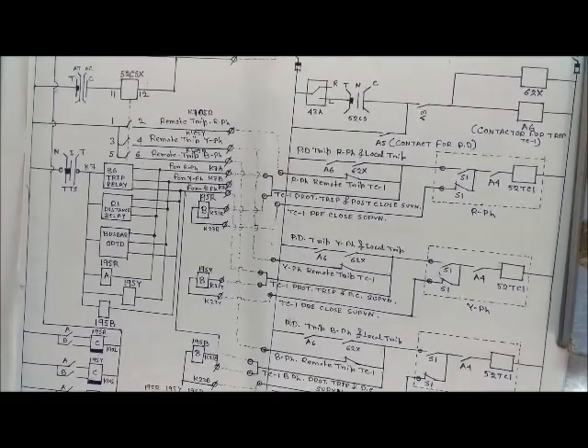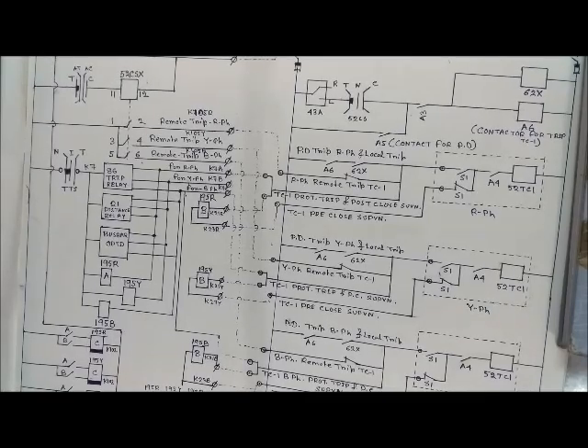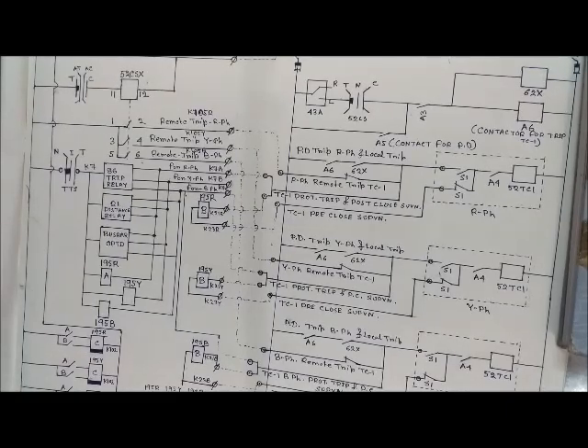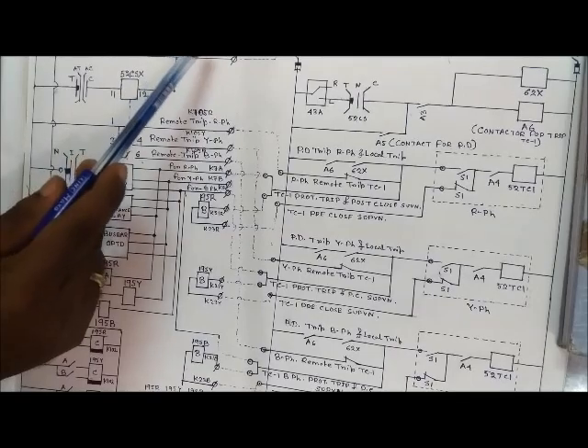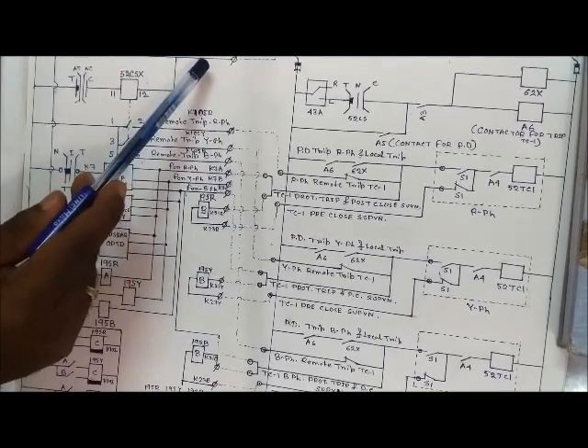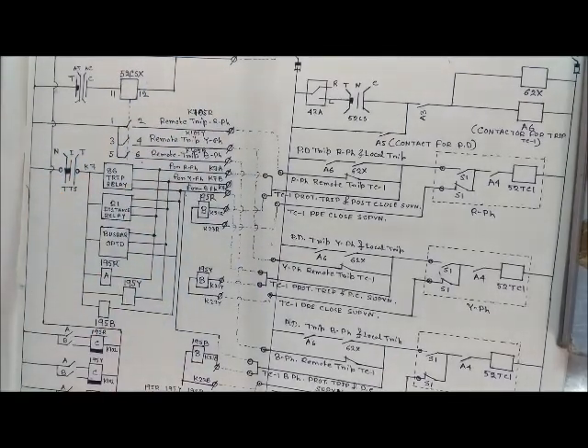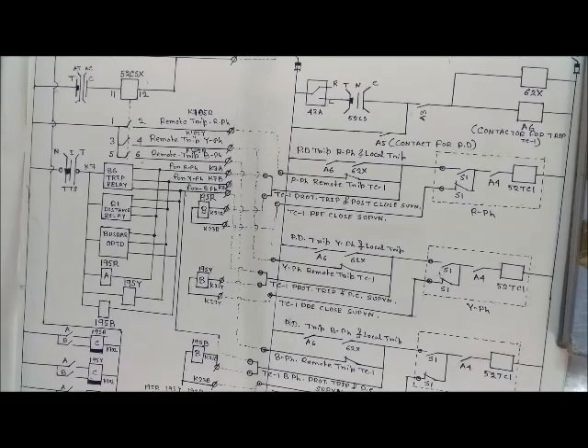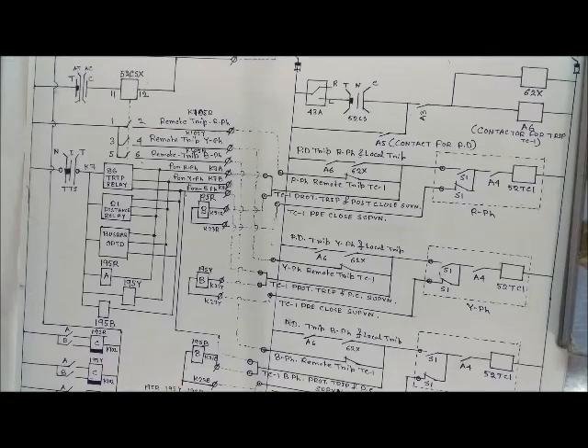This concludes the operation of the circuit breaker through trip circuit one. Similarly to trip circuit one, there is trip circuit two, which is not shown in this diagram. It is similar to trip circuit one — only the ferrule numbers change: for K101 it will be K201, for K102 it will be K202, and so on. If you like my videos, please visit my channel, subscribe, and press the bell button for future notifications. Thank you.